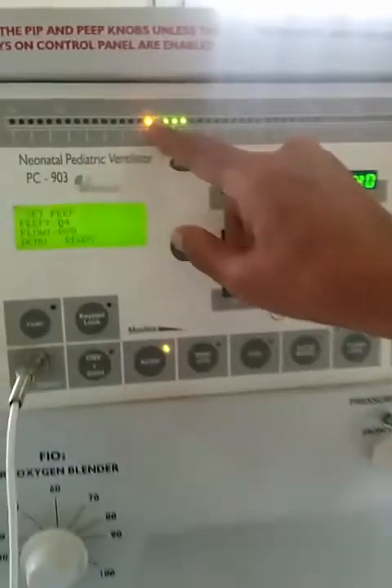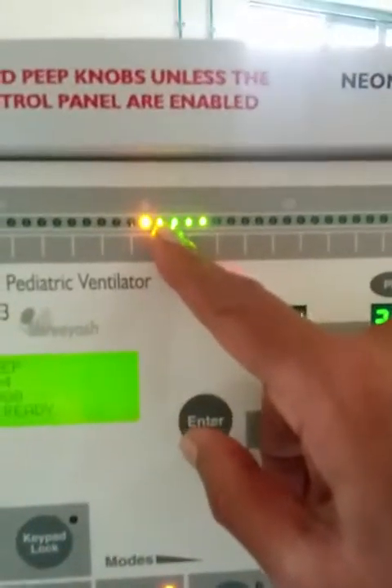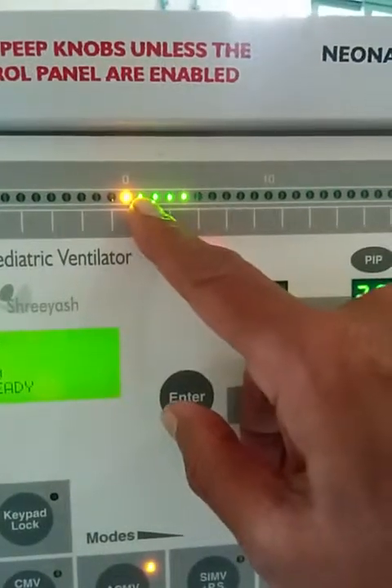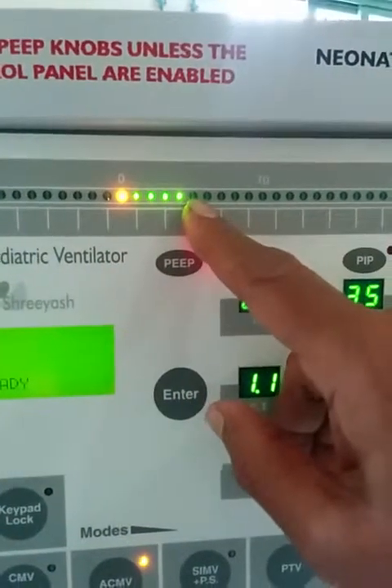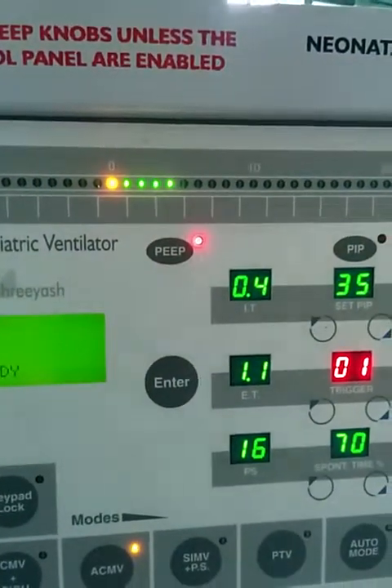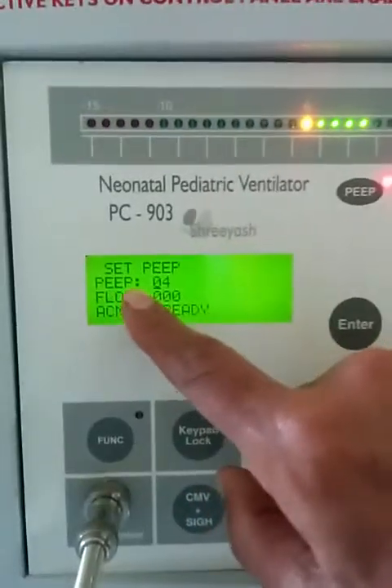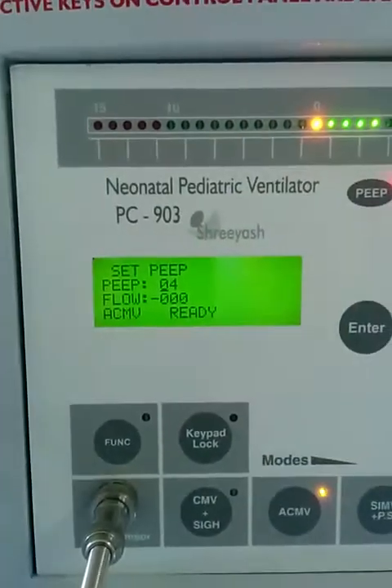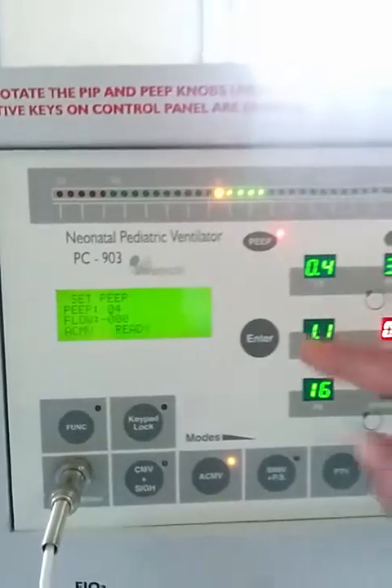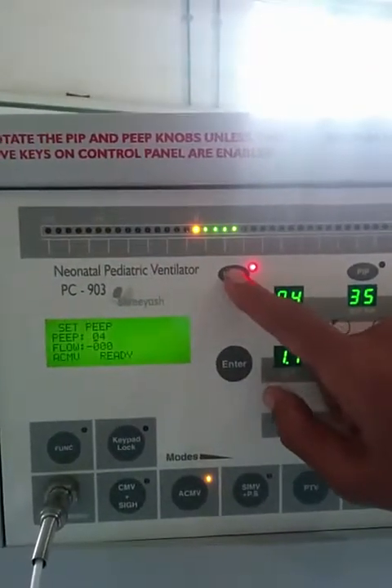So one LED corresponds to 1 centimeter of water column. These four green LEDs are lighting, so it's 4 centimeters of water column, and it's again displayed here on the alphanumerical display. Once the PEEP is set, acknowledge the setting by pressing the PEEP key.